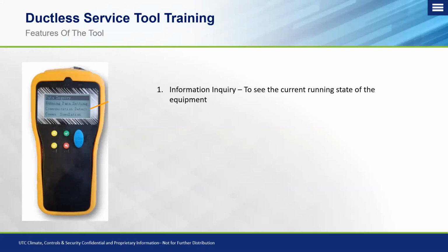The biggest thing to understand on here is that this tool, because of where it comes from and where this equipment was originally founded, is displayed in degrees Celsius. So you need to convert whatever your reading is on there to degrees Fahrenheit to make sure that we're reading it properly.